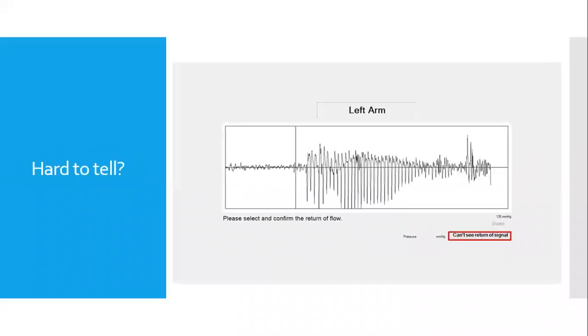Selecting the return of flow is not always easy. Due to patient movement, calcified arteries, or other reasons, the return of flow isn't always as easy to select. Luckily, for cases like this, there is another option for the PADnet device to automatically select the return of flow for you. By clicking Can't See Return of Signal, the PADnet software will use pneumoplethysmography to calculate a systolic pressure.